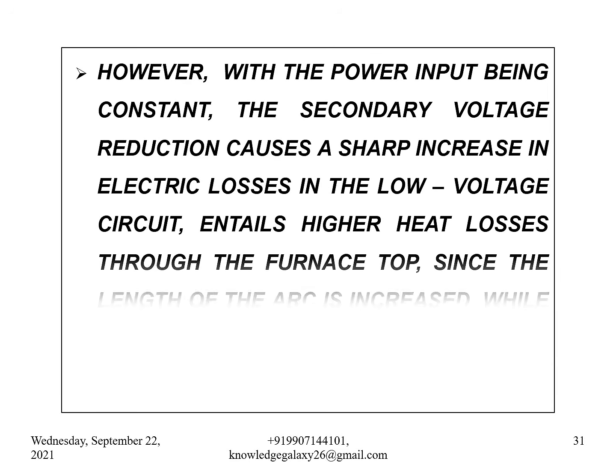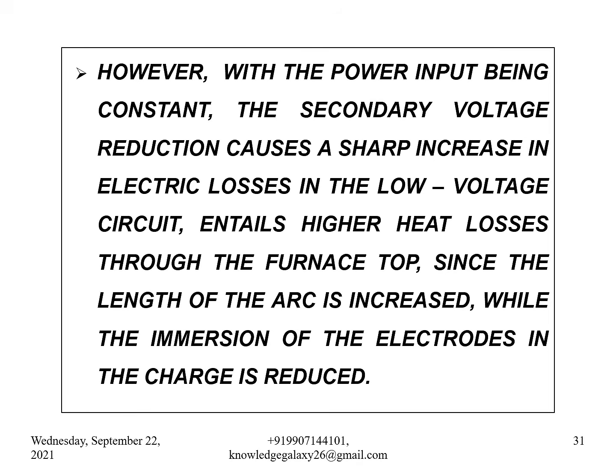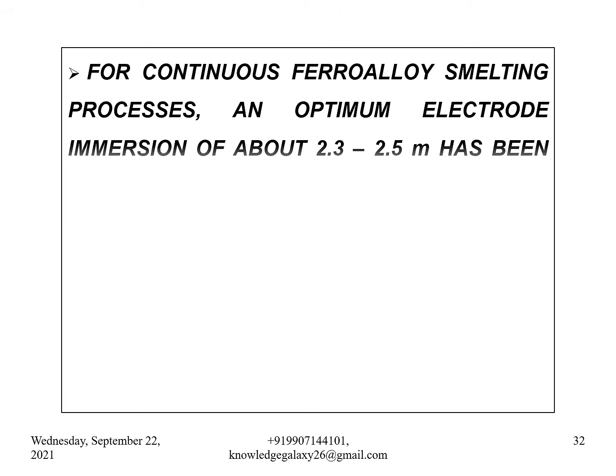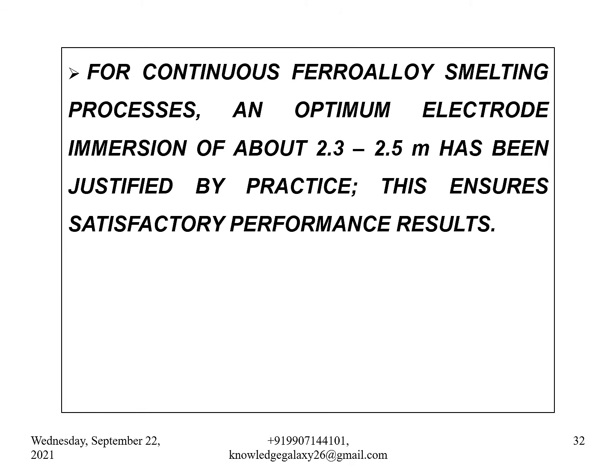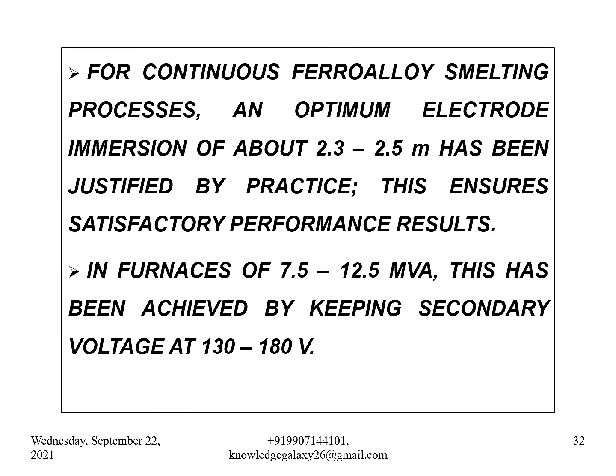However, with the power input being constant, the secondary voltage reduction causes a sharp increase in electric losses in the low voltage circuit, and entails higher heat losses through the furnace top, since the length of the arc is increased while the immersion of the electrodes in the charge is reduced. For continuous ferroalloy smelting processes, an optimum electrode immersion of about 2.3 to 2.5 meters has been justified by practice. This ensures satisfactory performance results. In furnaces of 7.5 to 12.5 MVA, this has been achieved by keeping secondary voltage at 130 to 180 volts.